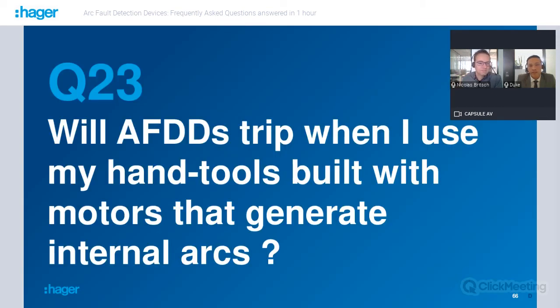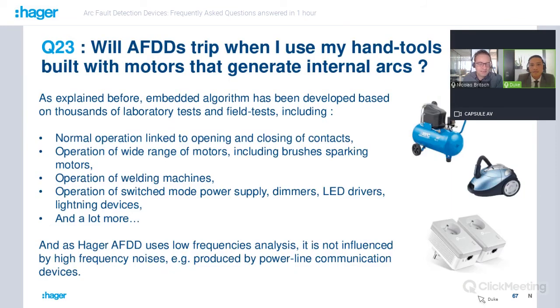Okay, so does the AFDD trip when I use my hand tools, for example a drill, with motors that generate internal arcs? This is also a question that we have sometimes, and people are maybe afraid that it could happen. But as explained before, the embedded algorithm has been developed based on thousands of laboratory tests, including, of course, normal operation linked to opening and closing of contacts, operation of a wide range of motors, including brush sparking motors, operation of welding machines, switched mode power supplies, dimmers, LED drivers, lighting devices, and a lot more. And as the Hager AFDD uses low frequency analysis, it is also not influenced by high frequency noises that we can find, for example, produced by power line communication devices. So there is no problem with this kind of appliance.